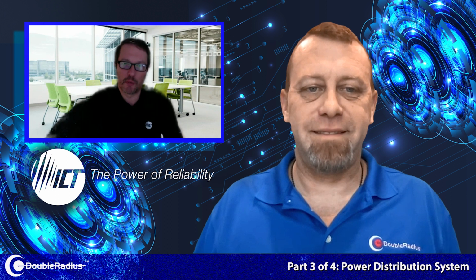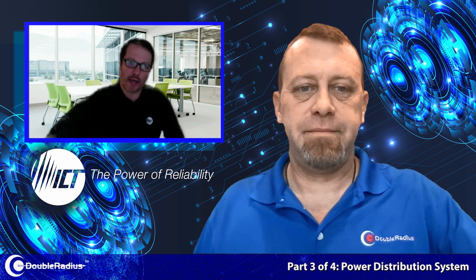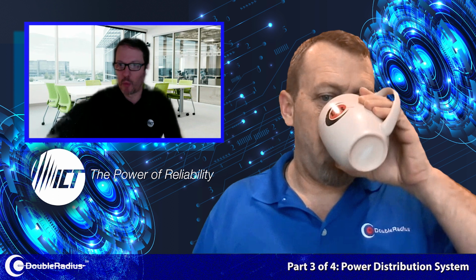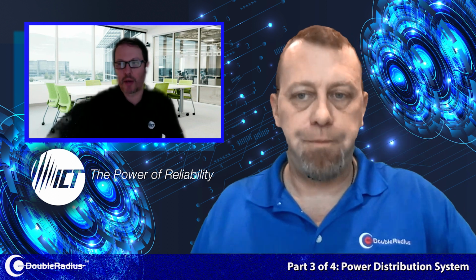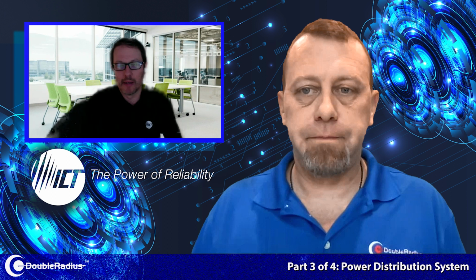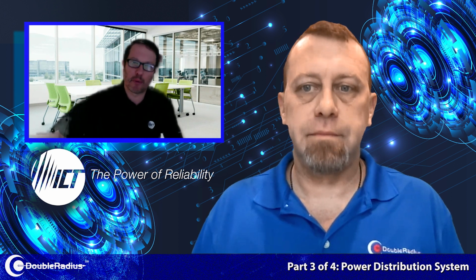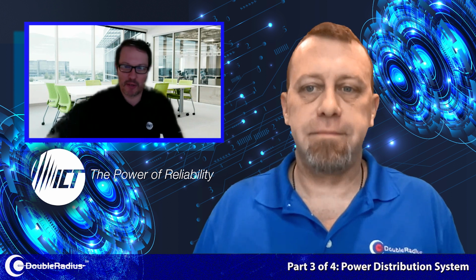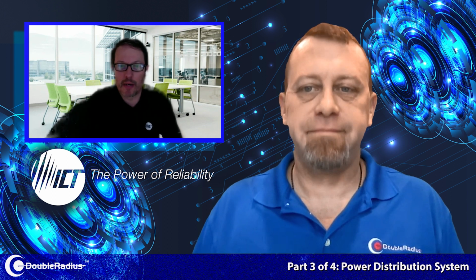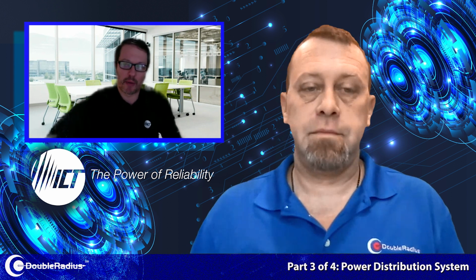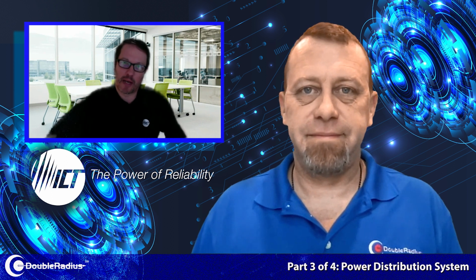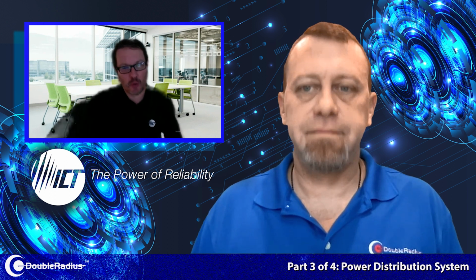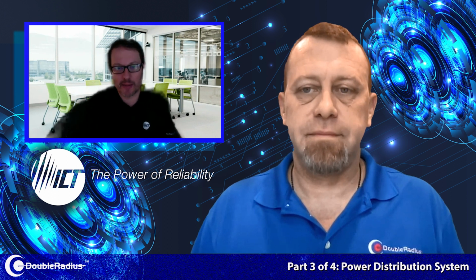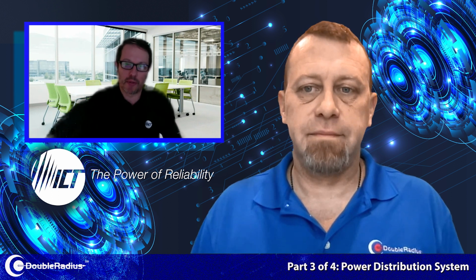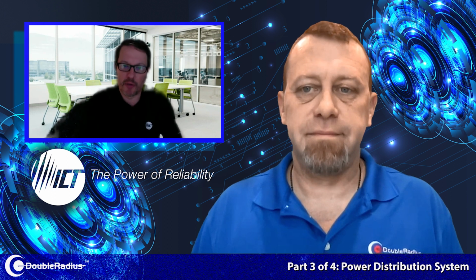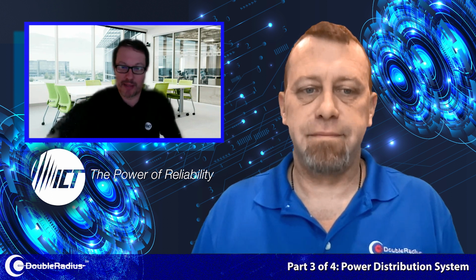And then we have our dual bus distribution panels, and those ones are used generally when there is more than one voltage at the site. So quite often you have 48 volts primarily for most of your load devices, and there may be some peripheral devices there, maybe two or three devices that need 24 volts DC to operate. So having a dual bus distribution panel enables you to have 48-volt devices connected on one of the buses, and then the 24-volt devices connected on another bus, and being able to monitor all those outputs, again, through our graphical user interface, and control the devices as needed.